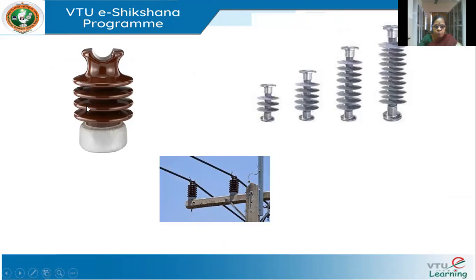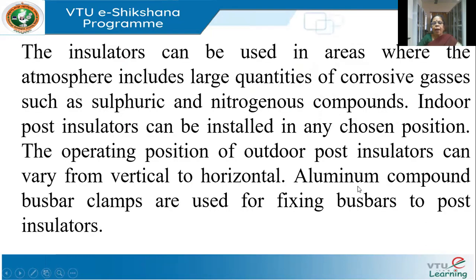This is a porcelain post insulator and these are all silicone post insulators. This is how it will be mounted on the cross arms of the pole — this is called a cross arm. They can be used in areas with more number of petticoats than a pin type, so they're more robust to pollution. You can use them where the atmosphere has large quantities of corrosive gases like sulfuric acid and nitrogenous compounds.